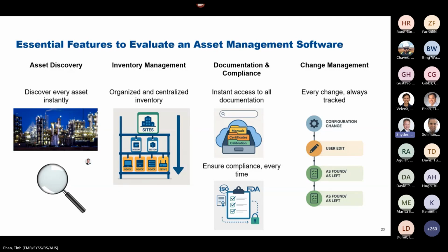A system like an asset management system needs to get all the information from those devices. A vibration transmitter, believe it or not, has over 400 different parameters. A control valve may have 150 parameters. Some simple temperature devices may only have 80, but pulling all that information in is much easier with an online system that can scan and read it all in.